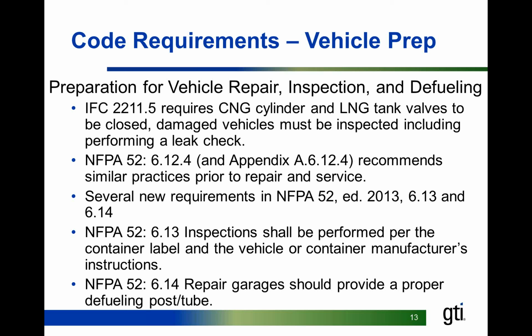Another part that is not addressed as often when looking at facilities is vehicle prep. So when you talk about how to operate a shop, getting the right procedures in place is very important to the whole process. Typically, for all fuels, there are code requirements to close the valve from the fuel tank, and also to make sure that the vehicle is not leaking fuel before it comes in. That's seen in IFC as well as in NFPA 52. There are several requirements in NFPA 52. Chapter 6, Sections 13 and 14 have a lot of very good detail on procedures and defueling of a vehicle before it enters, when that is necessary, and how to perform that.